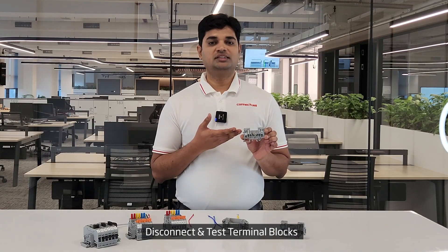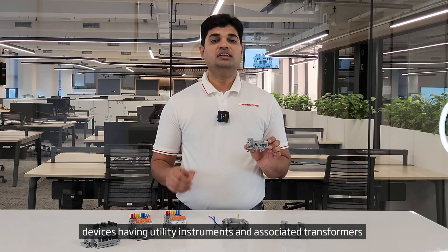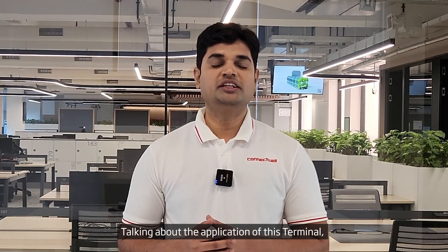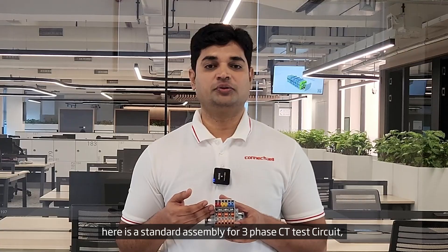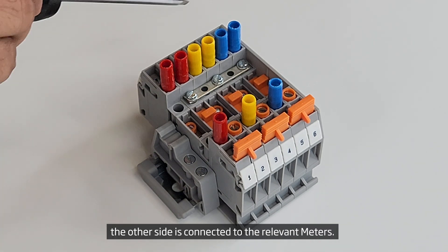Connectwell CDS-SITSU disconnect and test terminal blocks provide a clear functional advantage for devices having utility instruments and associated transformers. These terminal blocks are suitable for wires crimped with pin-type ferrules. It is very easy to create complex CT circuits using CDS-SITSU terminals. Here is a standard assembly for a three-phase CT test circuit, where the S1 and S2 wires from the CTs are connected on one side of the terminal assembly and the other side is connected to the relevant meters.